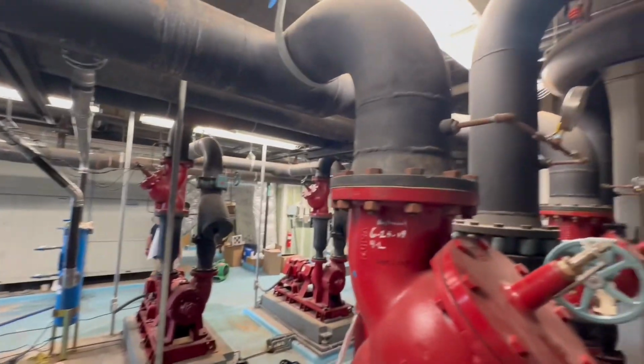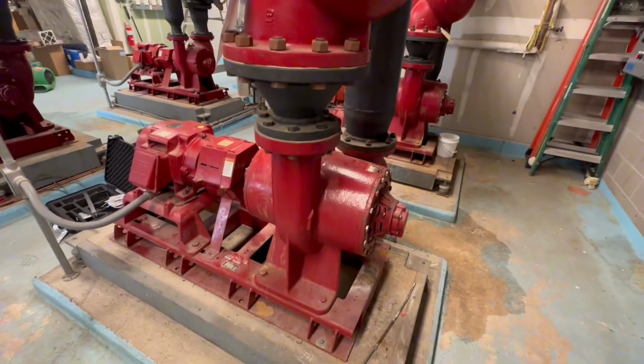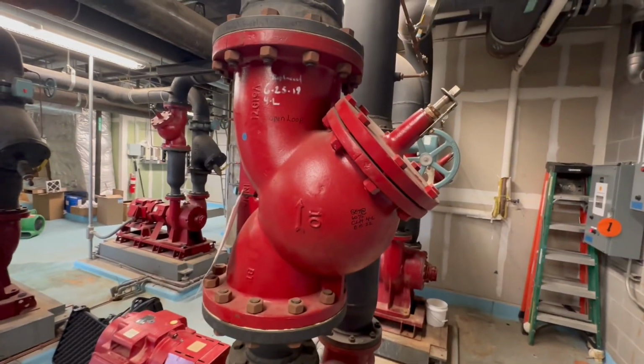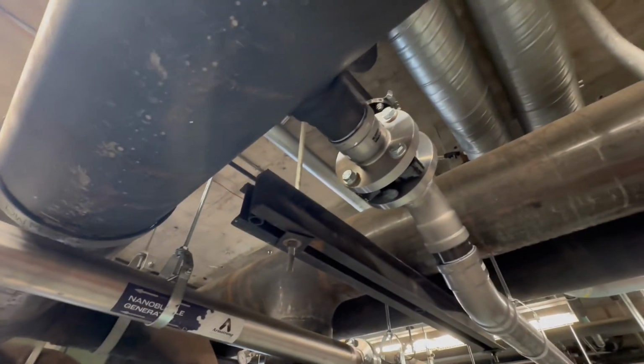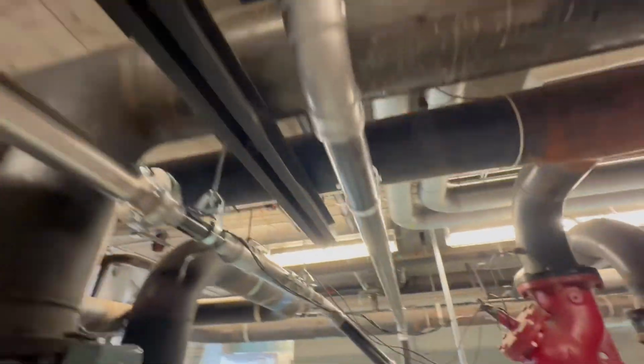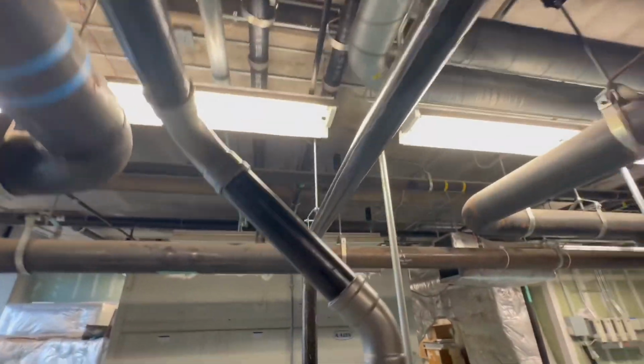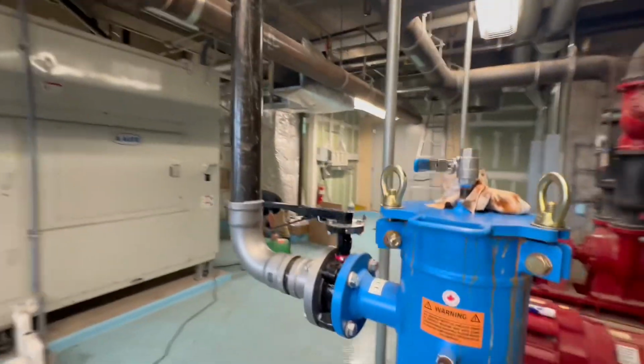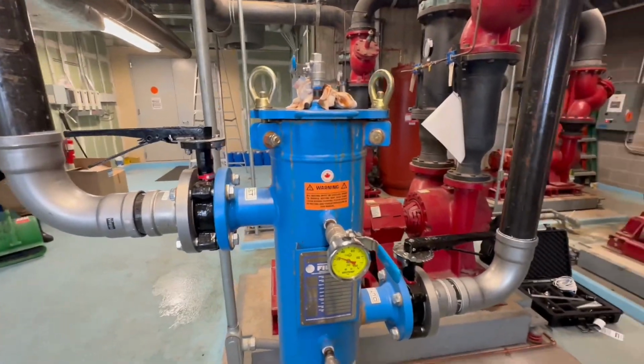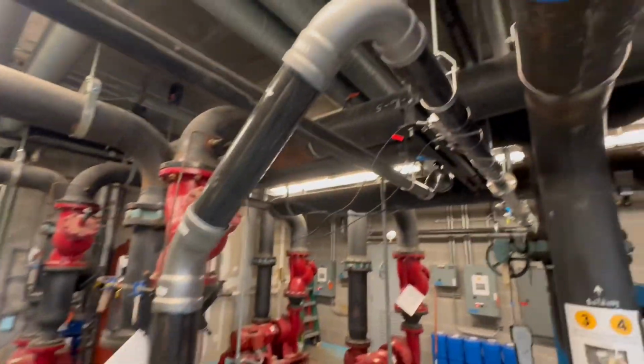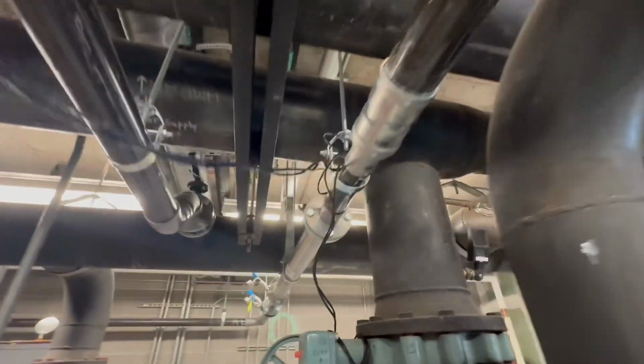So what we have here is a line tapping off the discharge side. So here's the discharge side of the condenser water pump right here. Then here's our tap right here. They tapped into the condenser water line with the 3-inch line. The 3-inch line runs down through here, over through the bag filter so that we can catch all of the debris. Out of the bag filter, we run up here into the nanobubble generator.